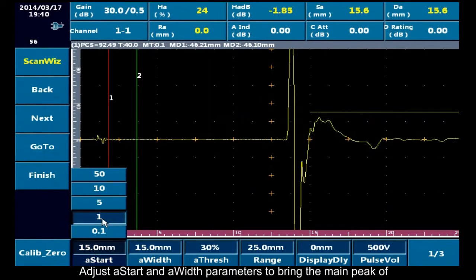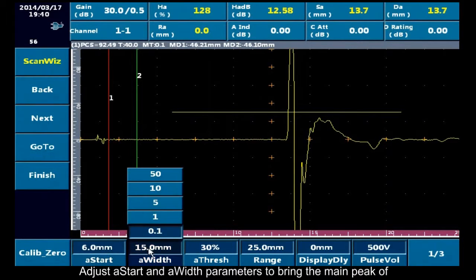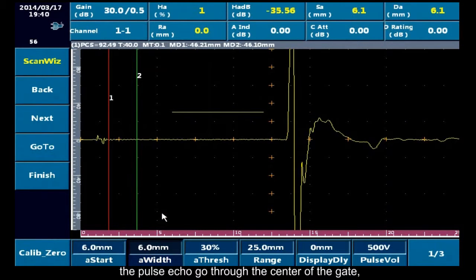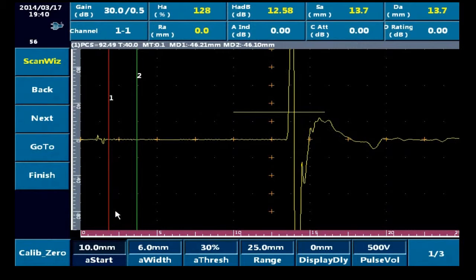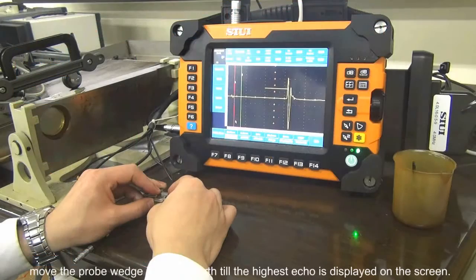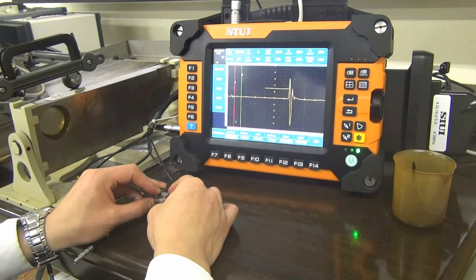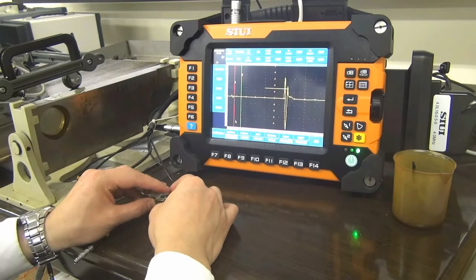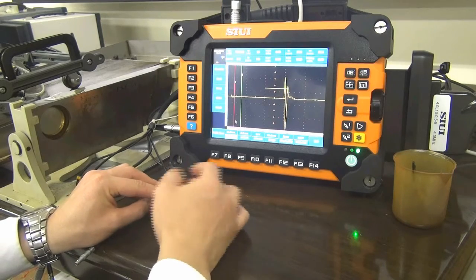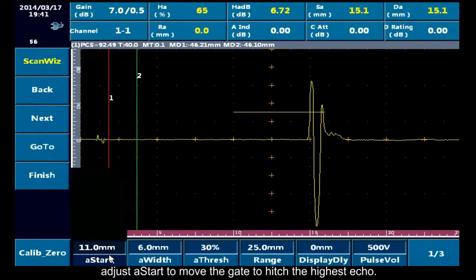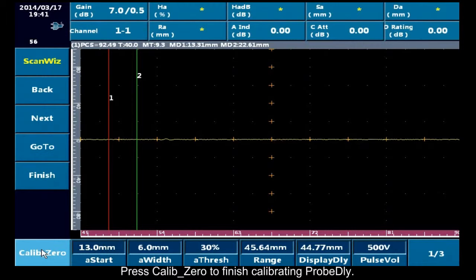Adjust A start and A width parameters to bring the main peak of the pulse echo through the center of the gate. Move the probe wedge back and forth till the highest echo is displayed on the screen. Stabilize the probe. Adjust A start to move the gate to hit the highest echo. Press calibration 0 to finish calibrating probe delay.